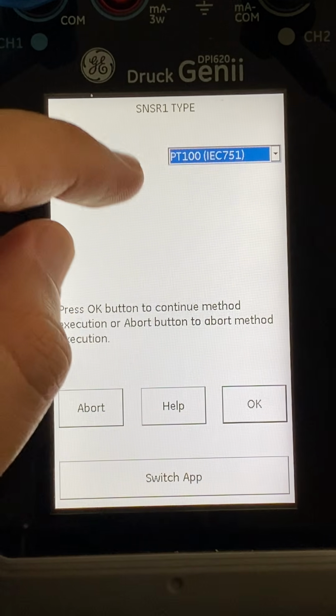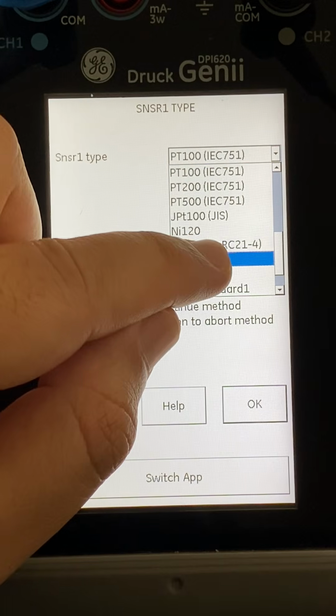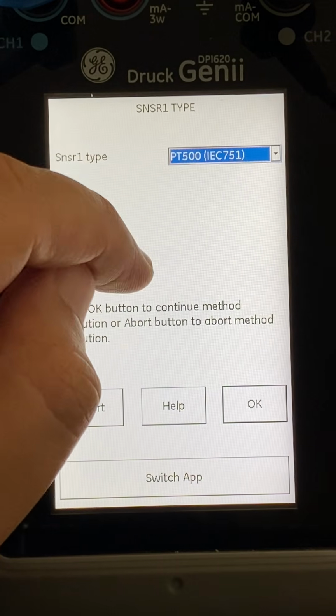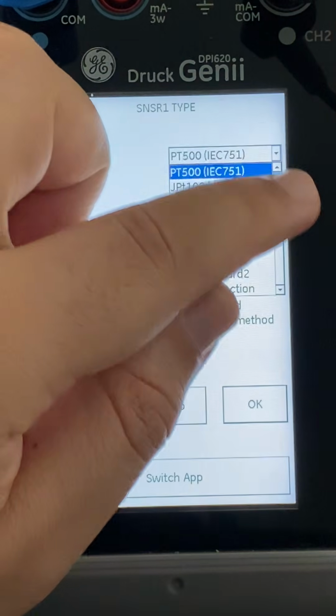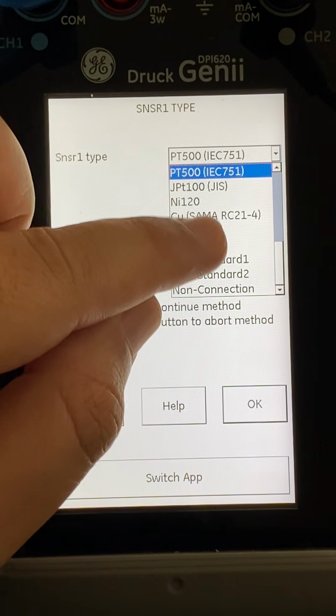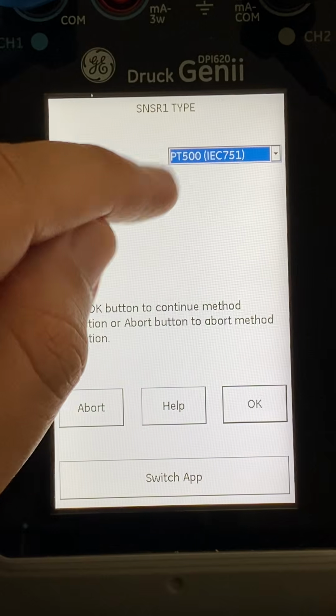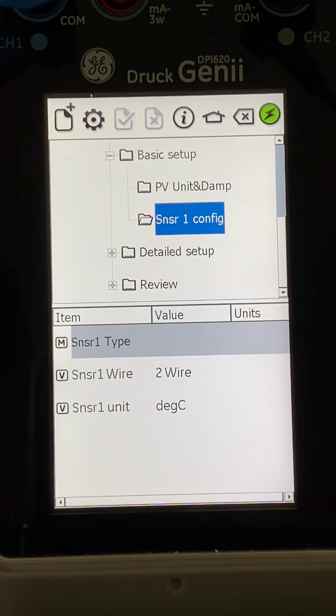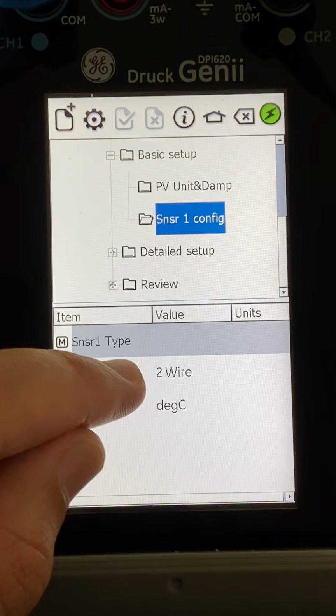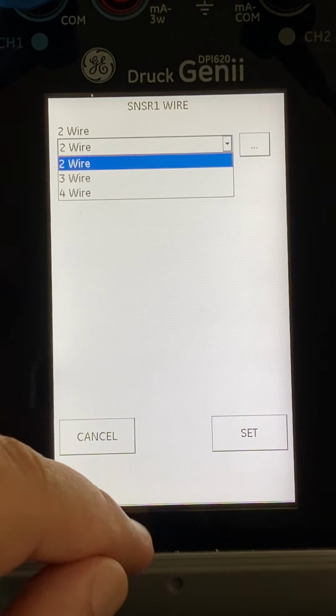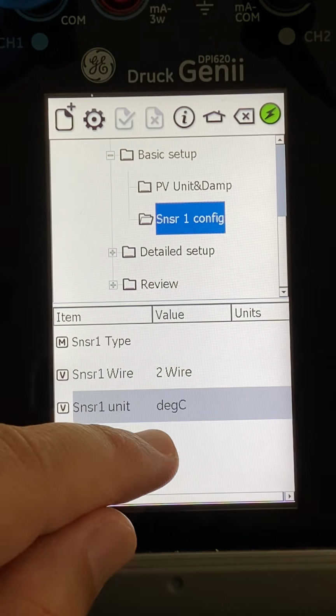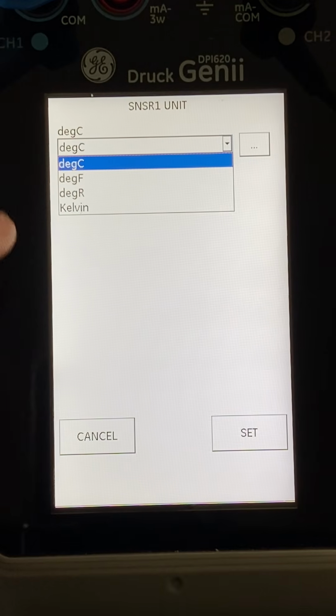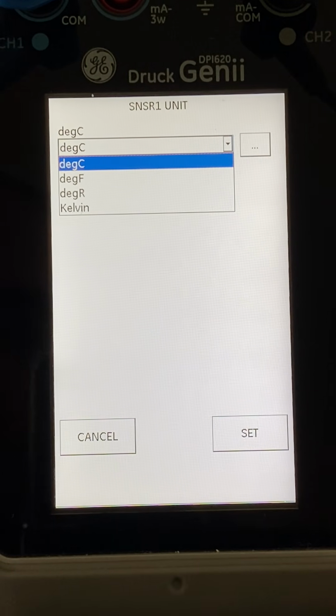Let's change it, for example, to PT1000. Okay. It looks like it's not in the transmitter. PT200, PT500, these are uncommon things which we have never seen before. I don't know about you, but I have never come across them. Okay, or you can change it to thermocouple. Abort, no need. Okay, you can also change the configuration: 2 wires, 3 wires, or 4 wires. You can change the unit as well. So this device gives us 3 or 4 options: Celsius, Fahrenheit, R or K.